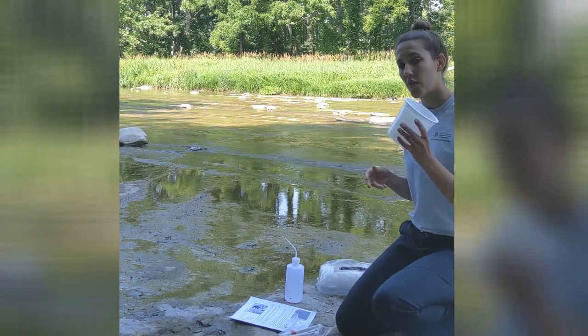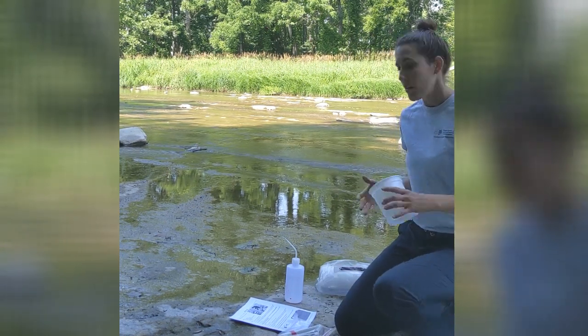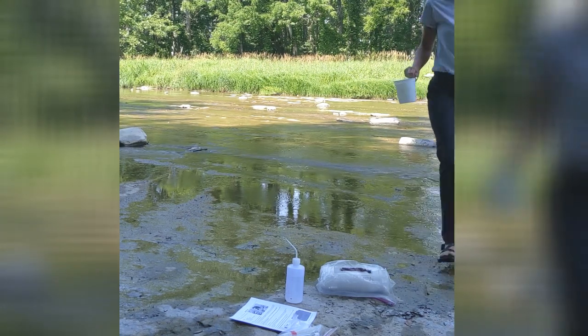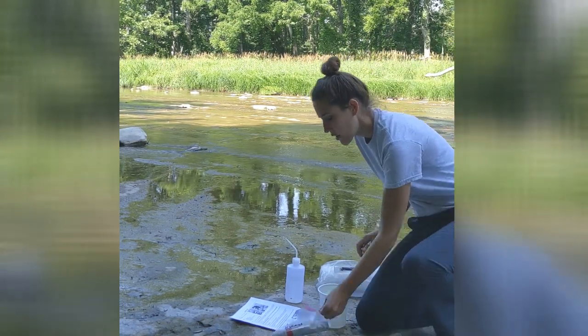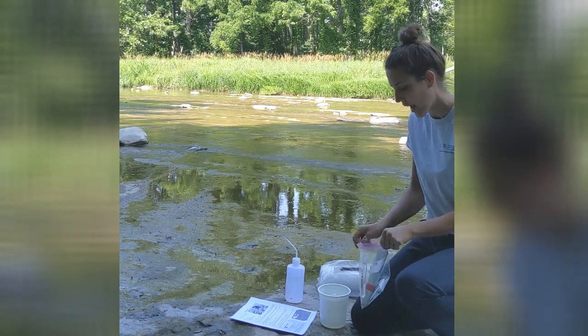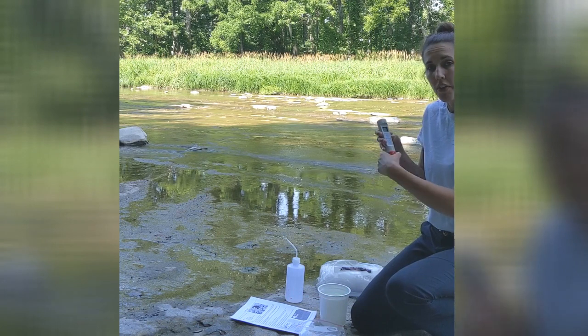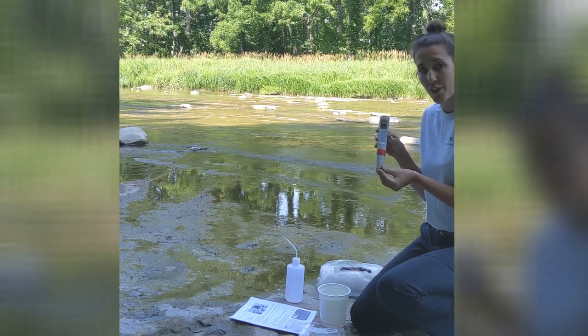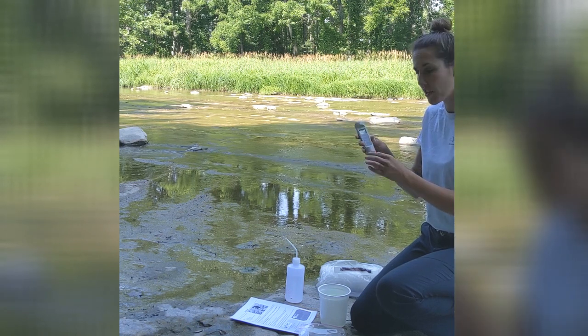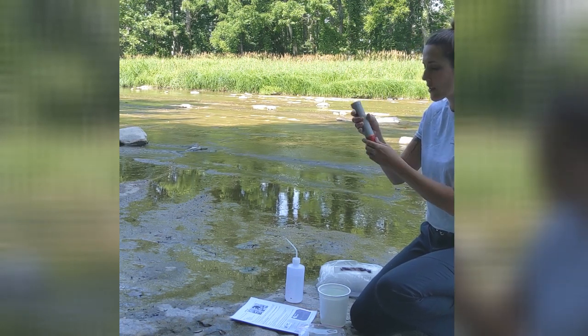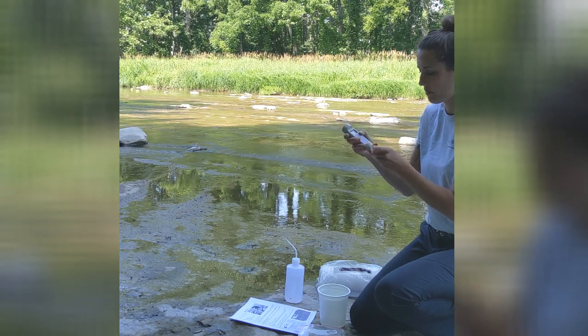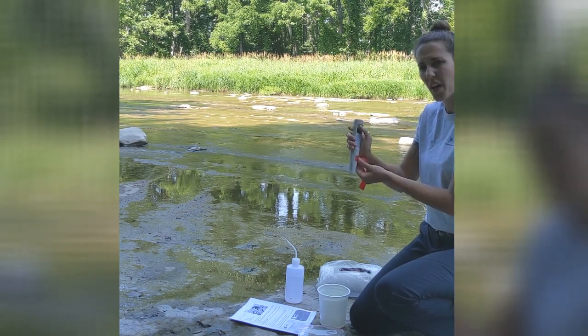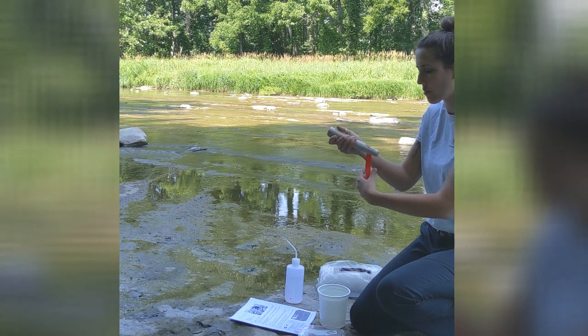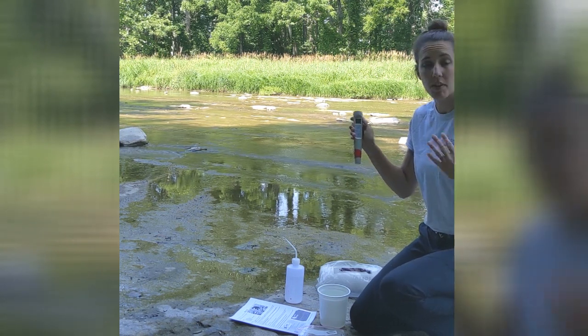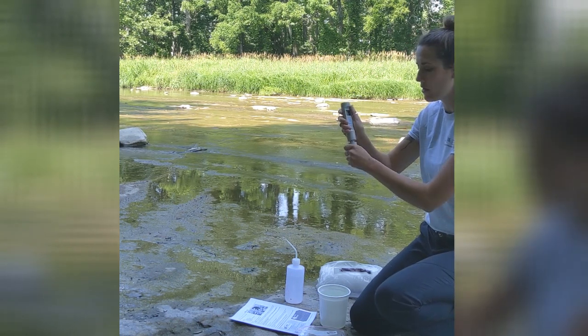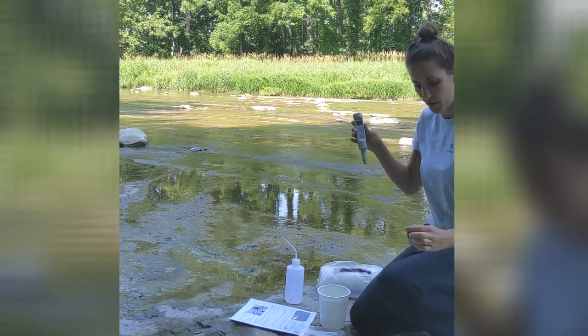The first thing we need to do is find our sample container and fill it with water. Then, when you get your meter, you might notice that it has some tape around the bottom. That's keeping the storage solution in our cap in our container. So the first thing you want to do is, holding your probe upright, just carefully remove that tape. We'll try to use it and keep it on there at the end of the day, so you can just wrap it around the bottom of the cap. Now the cap doesn't twist off at all, it just pulls straight down, and that will remove the cap for you.